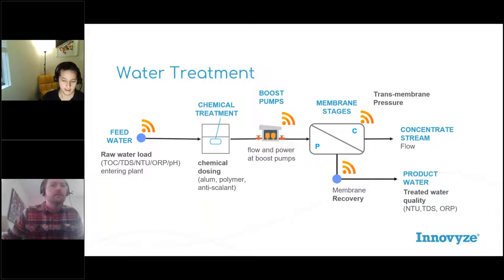Ultimately, when we look at water treatment or wastewater, we underlie those models with a compliance model that looks at the system as a whole. It's an operations management system using the constraints of whatever permit you have - if it's a wastewater discharge permit, that may have ammonia and other nutrient limits, and for water treatment, suspended solids limits and NTU. We look at those limits, set that as a base model, and apply a risk factor to that risk model.